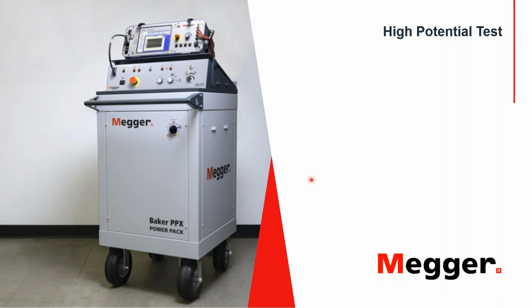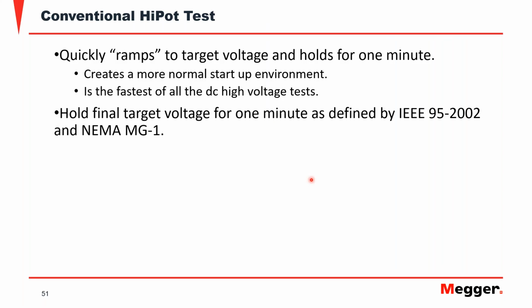The high potential test, what you do with the high potential test is you inject, and remember, all of these are DC tests. Again, I mentioned that you can do AC HiPot tests, but the tests that we are discussing today are DC HiPot tests, okay? So what you do for the HiPot is you inject a high voltage that is typically way higher than the nominal voltage of the winding.